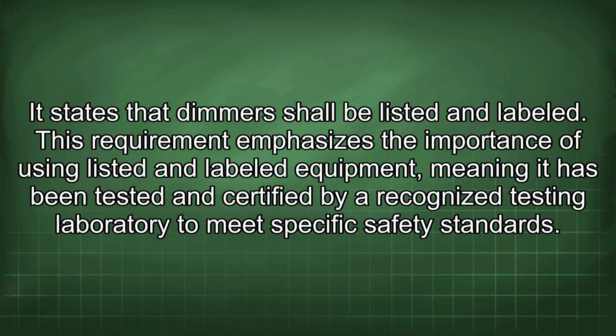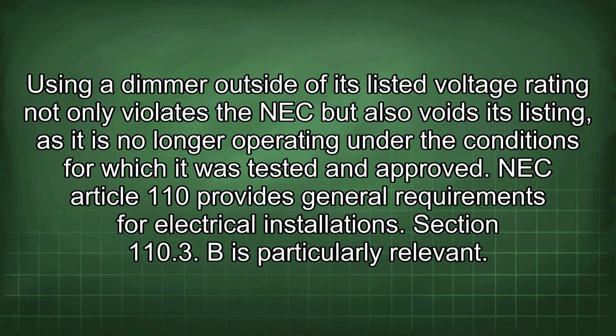This requirement emphasizes the importance of using listed and labeled equipment, meaning it has been tested and certified by a recognized testing laboratory to meet specific safety standards. Using a dimmer outside of its listed voltage rating not only violates the NEC but also voids its listing, as it is no longer operating under the conditions for which it was tested and approved.